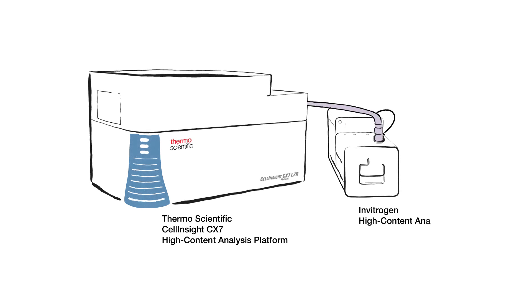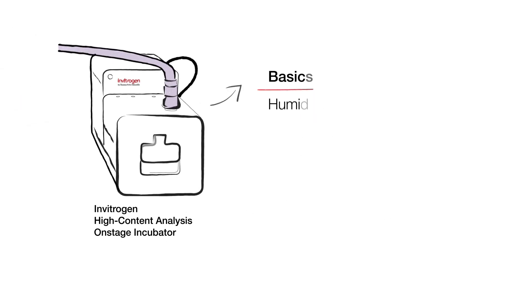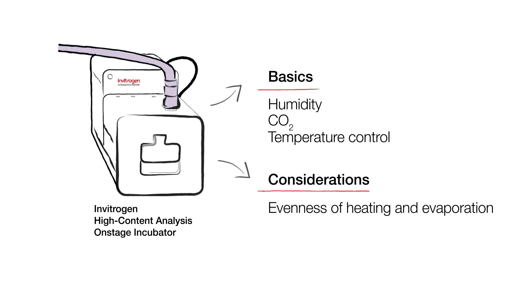Environment. Having realistic expectations is key. HCA systems are not tissue culture incubators — they are designed to keep a stable environment for the length of an assay. Humidity, CO2, and temperature control are the basics. Consider evenness of heating and evaporation, edge effects, and plate types when doing live cell HCA assays.